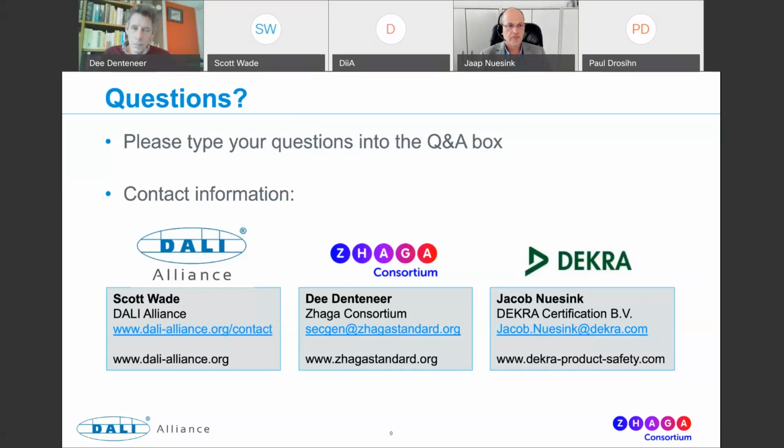Yeah, so this is applying to parts 252 and 253, the energy, power, and diagnostics parts. So we specify how to report this information, the power, the energy, voltage, and so on, including the formats, but we don't specify accuracy requirements, and that's quite deliberate. Our members don't want us to specify accuracy requirements. That's manufacturer specific. And the question is about including this in the data sheet, and that's a good point. We haven't added a requirement that the manufacturer shows that in the data sheet, but we'll consider that for the next update. So thanks for that.